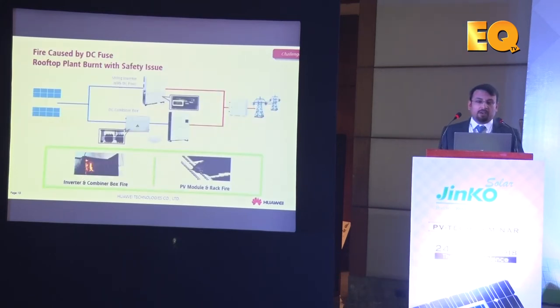One of the major problems we have seen in rooftop plants as well as ground mount—more serious for rooftop—is that if a fire happens, the building structure gets hurt and there's a problem for the building. So what we have come up with is a solution where we can detect any arc on the DC side and disconnect the whole system.